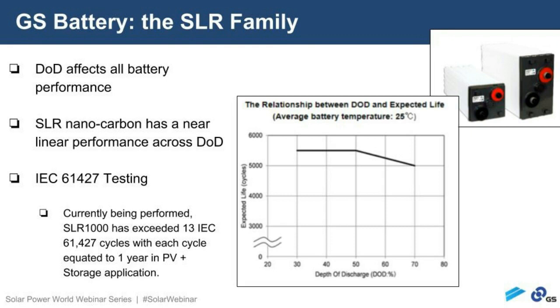Specific to the SLR family, and the SLR 1000 in particular, everyone is familiar with how depth of discharge affects battery performance and life. The nanocarbon battery has a near-linear performance across depth of discharge: at 70% depth of discharge you can expect about 5,000 cycles, and at only 50% depth of discharge you can expect about 5,500 cycles. So it's a pretty linear battery life based on depth of discharge, and that's all due to the nanocarbon enhancement.